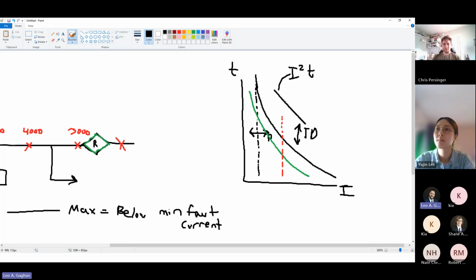really depends on the magnitude of that current and how long it is there. Right? A lot of current doesn't take long for things to break. And even if it's not a ton of current, if it hangs out for a long time, it's going to heat up over time. So you've got that I squared T for damaged equipment. Usually you're going to want to look at the piece of equipment you're protecting and say, okay, I need to be faster than that damage curve because I don't want it to be damaged.